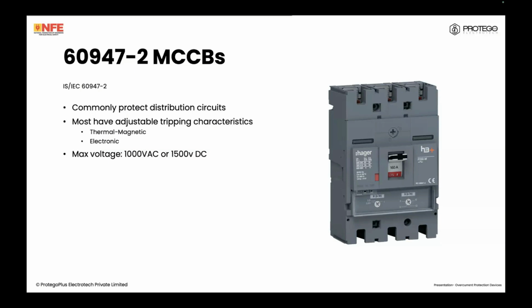Sure. So these MCCBs commonly come in an adjustable type. There are also some fixed types. We'll look at that a little later. Commonly, we have thermal magnetic, which is similar to the MCB. There's a thermal part that works for overloads, and there is a magnetic part that works for short circuits or faults of negligible impedance. We've also got electronic release MCCBs. These allow us to set things like time delays. I'll show you some tripping characteristics of those. These 60947 Part 2 MCCBs are certified for a maximum voltage of 1000 volts AC or 1500 volts DC.